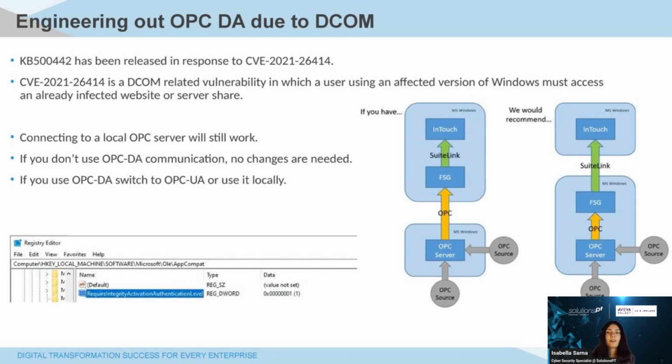Engineering out OPC DA due to DCOM should be high up on your priority list, as the changes to Windows over the last 2 years have made moving from OPC DA to UA a must.